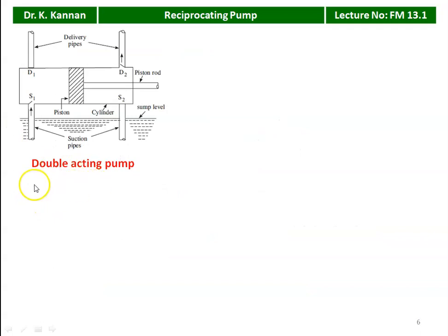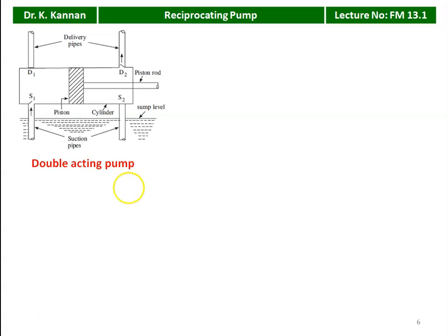In the double acting reciprocating pump, we have a piston reciprocating inside the cylinder with two suction valves (S1, S2) and two delivery valves (D1, D2) — one on each side of the piston. In the single acting pump, for every one revolution of the crankshaft there is one delivery. But in the double acting pump, for every revolution there will be two deliveries — delivery valve 1 delivers water and delivery valve 2 also delivers water, resulting in continuous delivery.